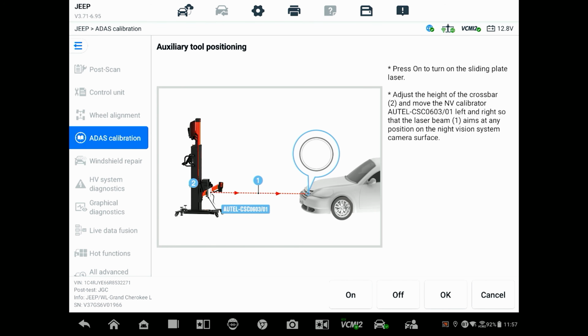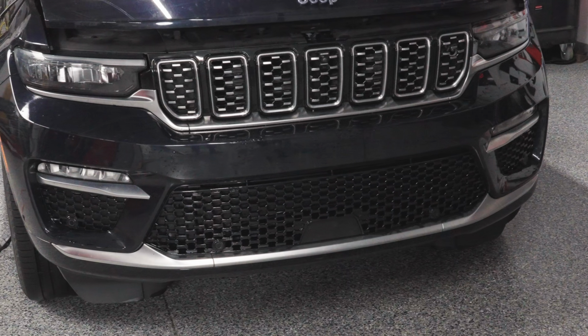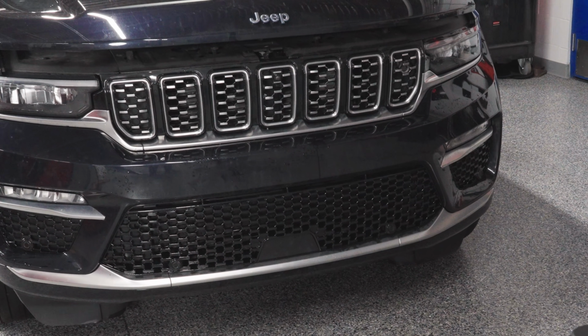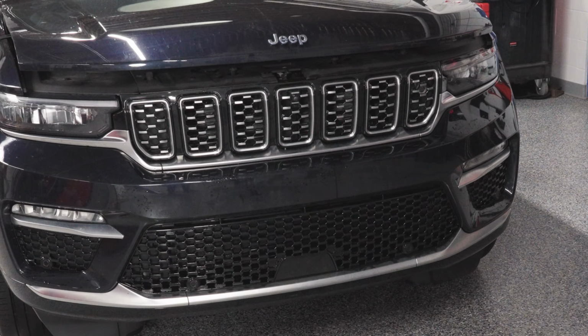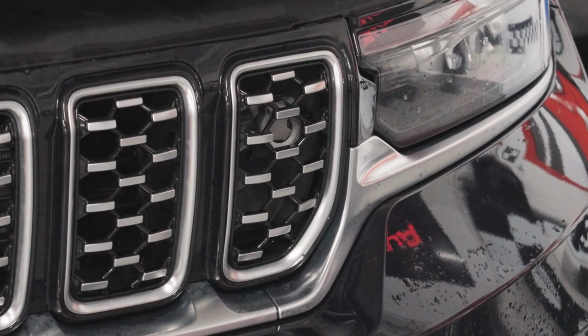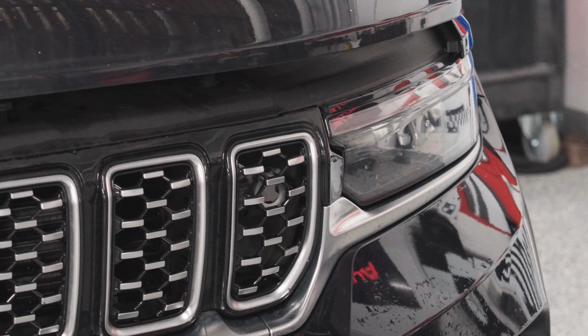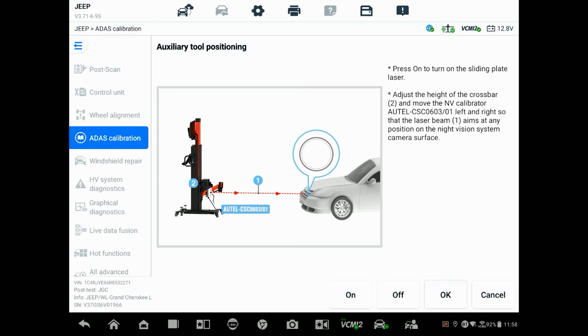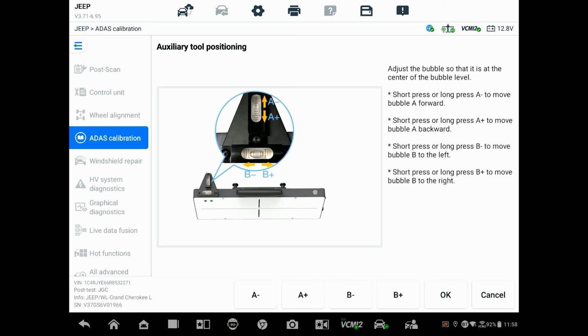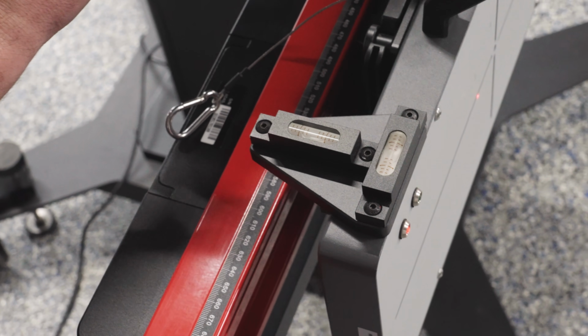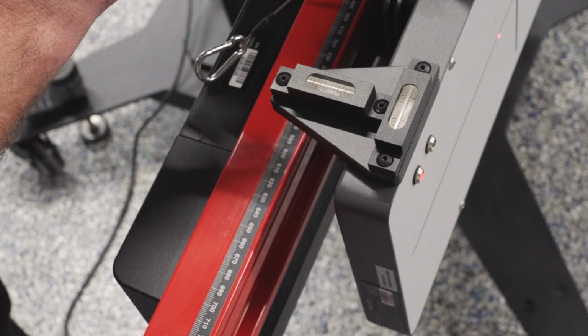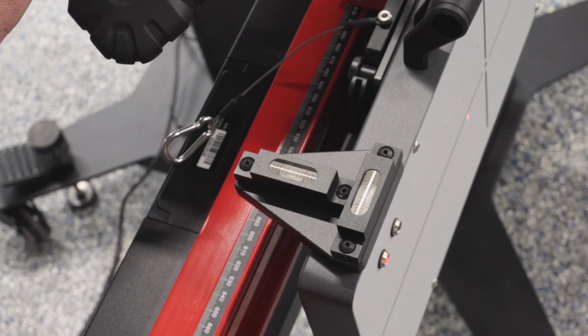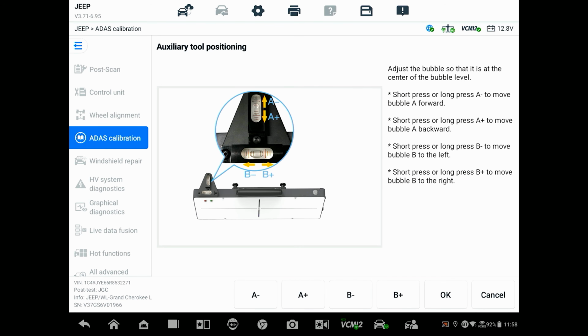Press on to turn on the sliding plate laser, and we'll adjust the height of the crossbar and move the calibrator left and right, whatever you need, so that the laser beam aims at any position on that camera surface. Kind of make those adjustments using your up and down and manually sliding that over. So I'm dead center on that night vision camera right now. So I'll press OK. Make sure now we're going to have to adjust the levels. Put this into position for you. And that is perfect. So we'll press OK.